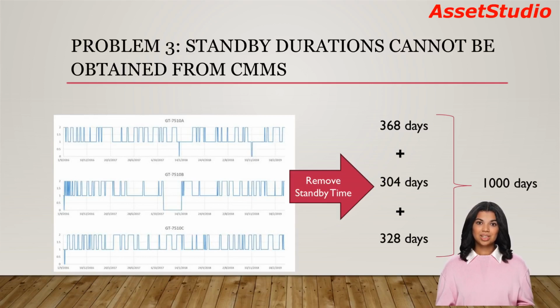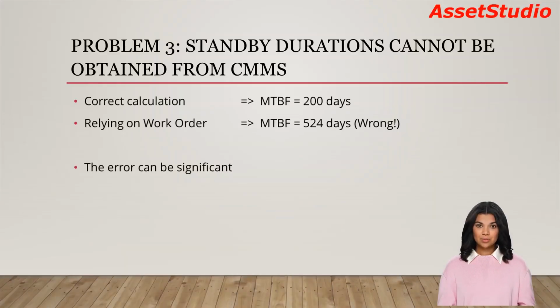First, derive the uptime of each unit as shown. Since we assumed that the 3 units are identical, we can calculate the MTBF by summing up the uptimes and dividing by total number of failures. In this case, the correct MTBF value is 200 days. Relying solely on CMMS work orders causes our results to significantly overestimate the reliability of the asset.